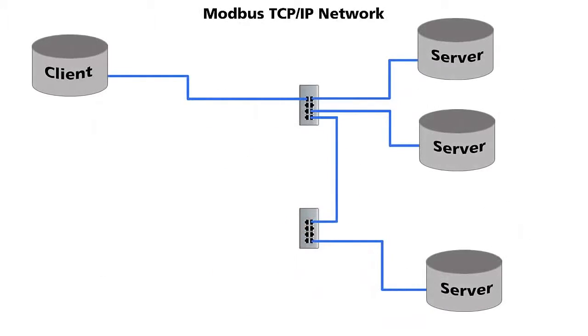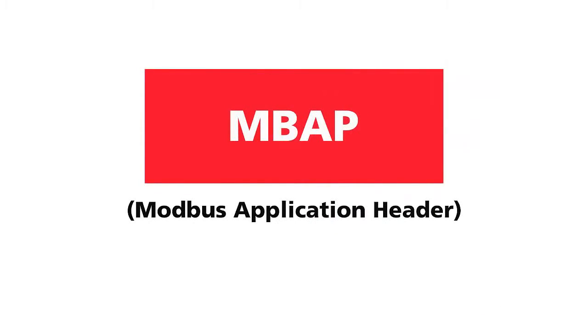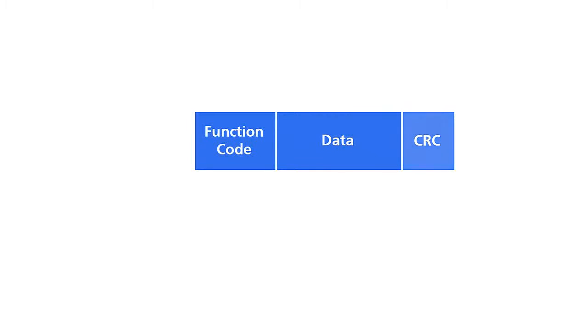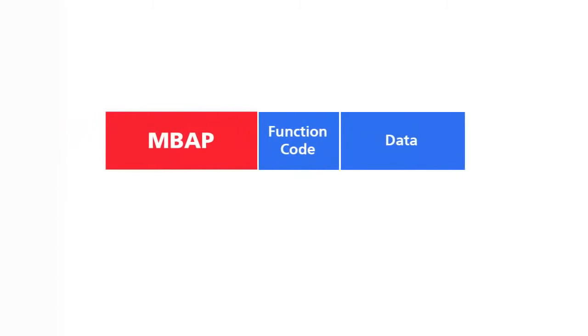Modbus over Ethernet operates exactly like it sounds: Modbus devices using regular Ethernet cables and switches to communicate with each other. The big difference with Modbus TCP IP is that an MBAP header, or Modbus Application header, is added to the start of each message. The slave ID at the beginning of the message is removed, as well as the cyclic redundancy check at the end. The MBAP header contains all the identifying information needed to route the data to the addressed device.